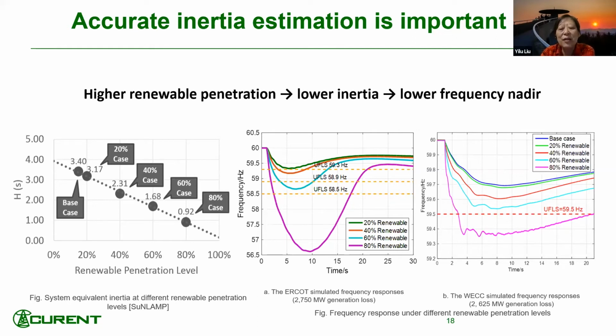If it has a good large inertia, it really doesn't move much, right? If it doesn't have a large inertia, it jumps, right? So now we're having a grid that starts to lose inertia gradually because renewables don't provide inertia, because they are not a mechanical device. You have a generator drop, you have a power loss because solar tripped.